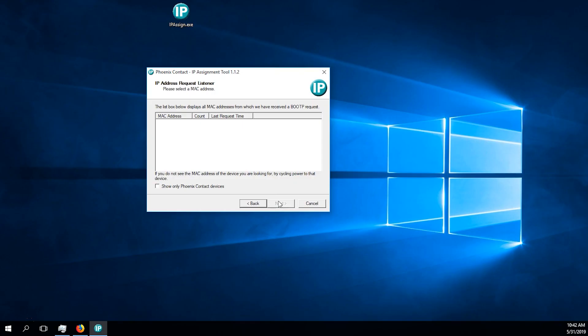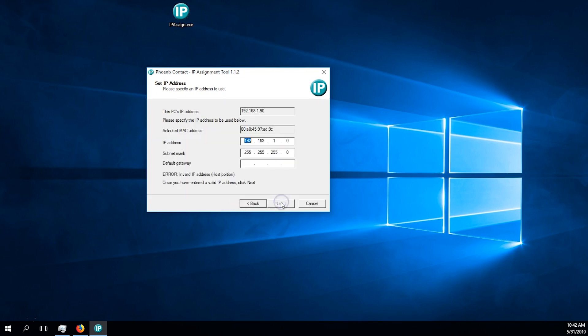We will now set up the station. Start by running the IP assignment tool. It will look for BOOTP requests sent out by the I.O. station. If nothing appears after a minute, try power cycling the I.O. station.